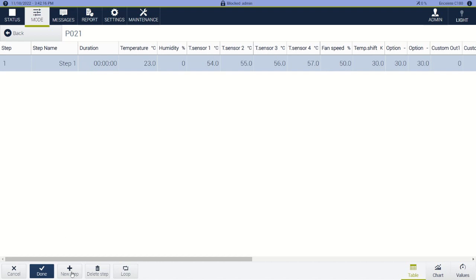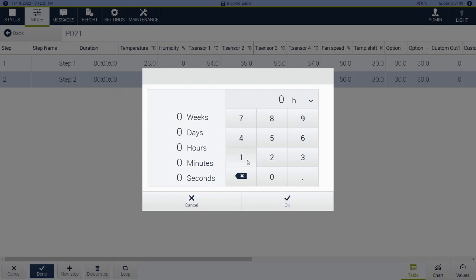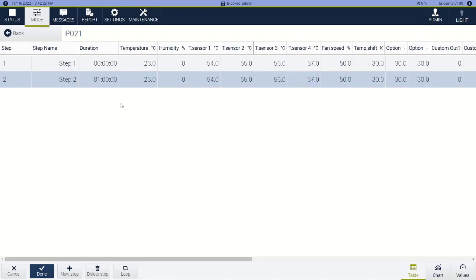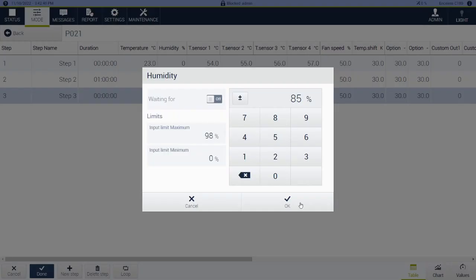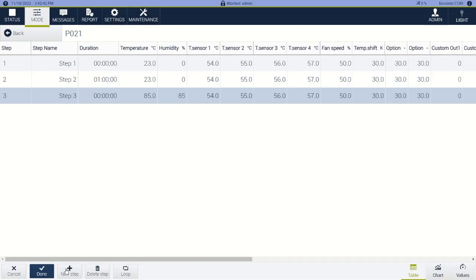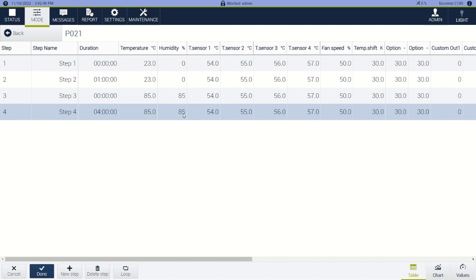And then we want a new step, so we click that. Let's say I want to stay for one hour — we could stay for seconds, minutes, days, or hours, but we'll just stick with hours. And we'll stay there. Next I want to jump — so duration of zero time — to 85°C, 85% relative humidity. And I want to stay there for let's say four hours. So I'll hit OK. 85, 85.